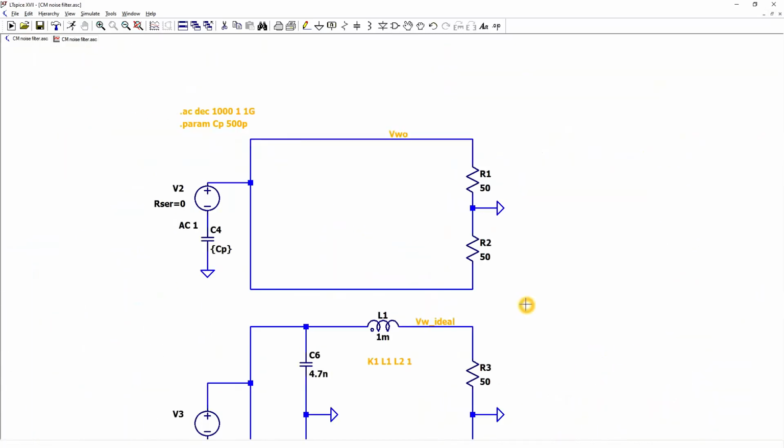For the common mode, in the conducted emission test setup, for example the test setup that you saw in part 1 of this series, the current from the source will flow through both conductors to the LISN impedance, then to the reference plane, and back through the parasitic capacitance to the source. The impedance seen by the noise source will be 25 ohm because the current from the source will split symmetrically.